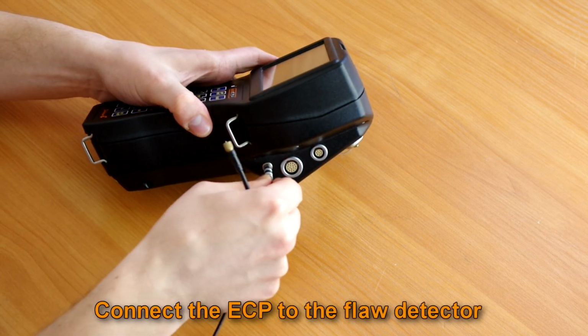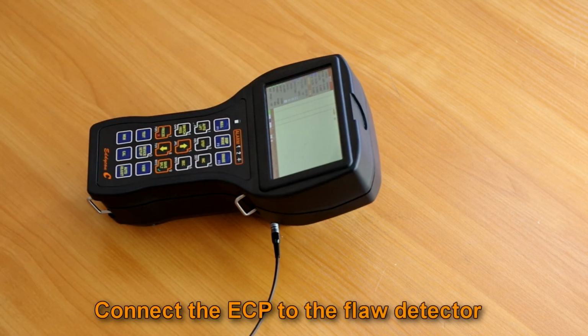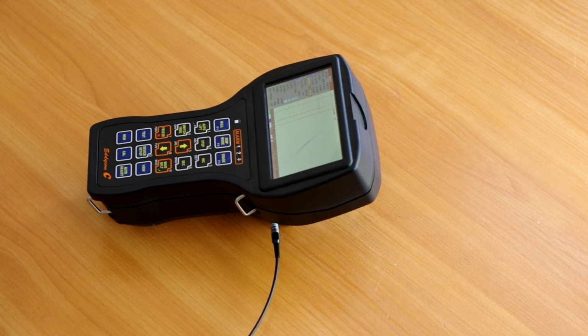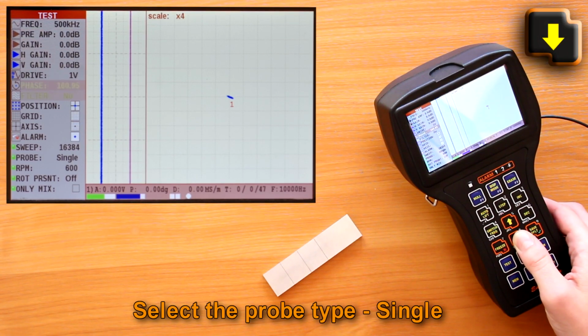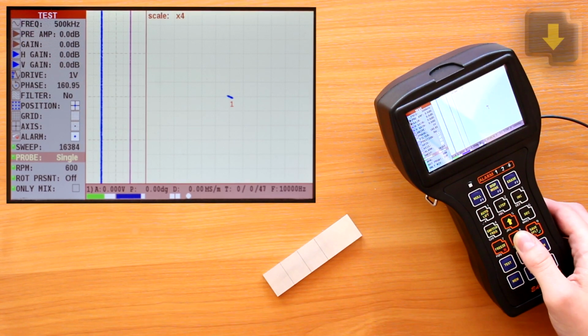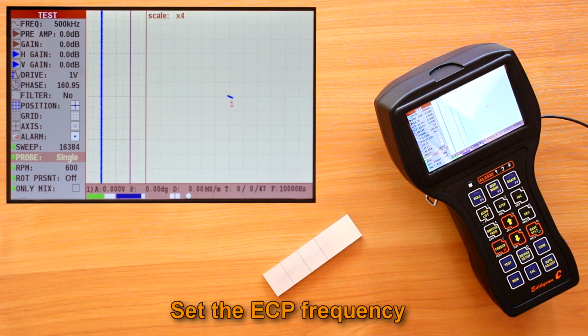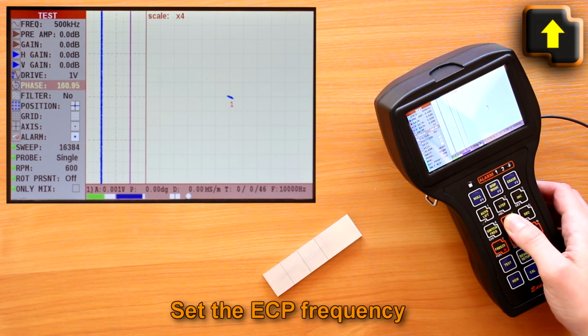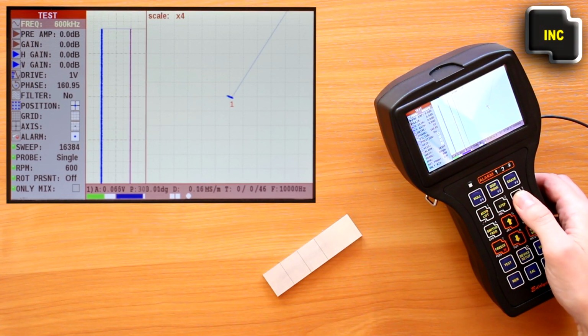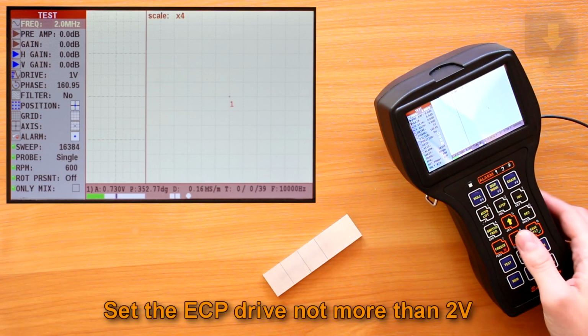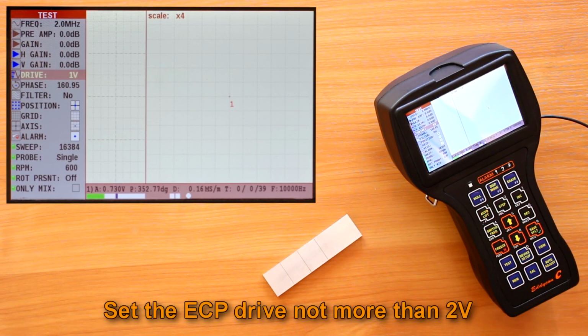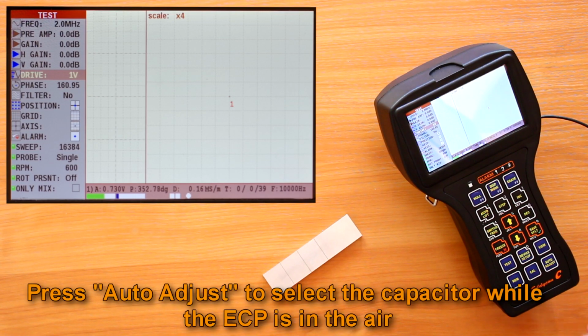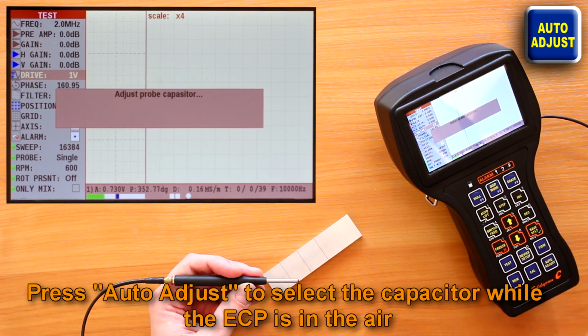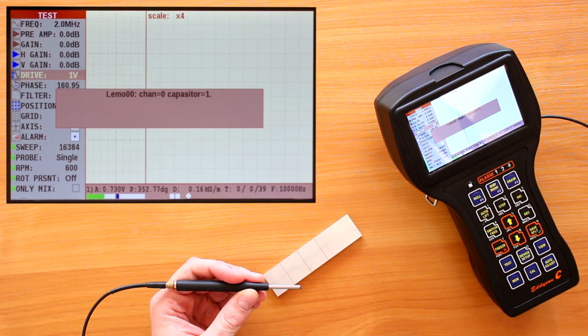Single coil probe. Connect the ECP to the flaw detector using a connecting cable. Select the probe parameter in the test menu, single type. Set the ECP frequency in a range specified in the registration certificate of the ECP. It also can be specified on the probe marking. At first, set the ECP drive not more than 2 volts. Press the auto adjust key to select the capacitor while the ECP is in the air.